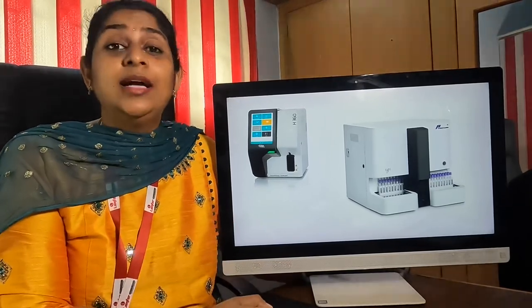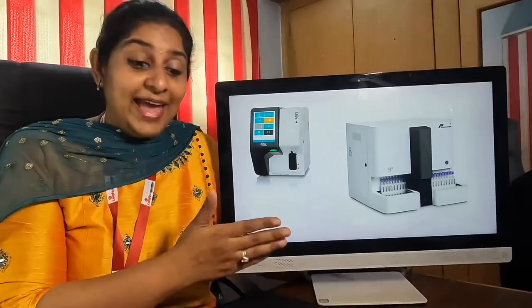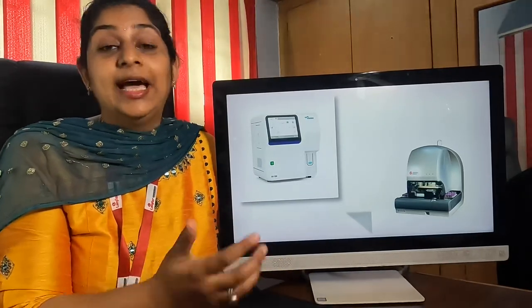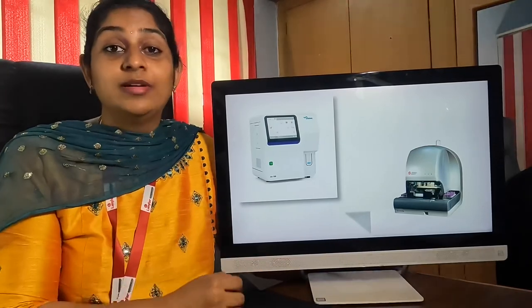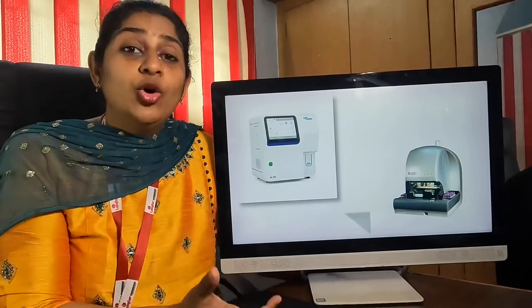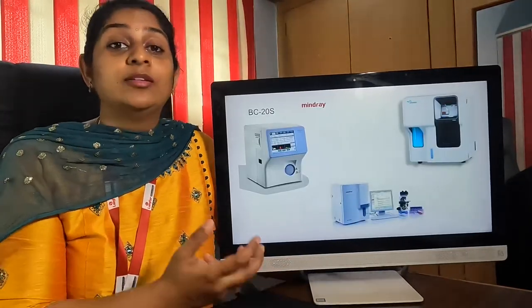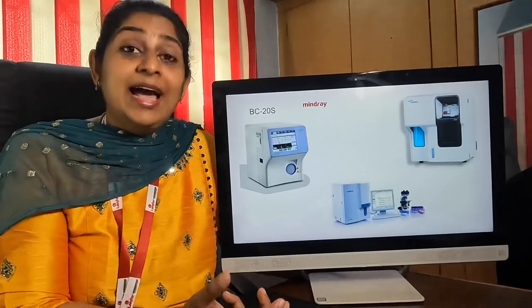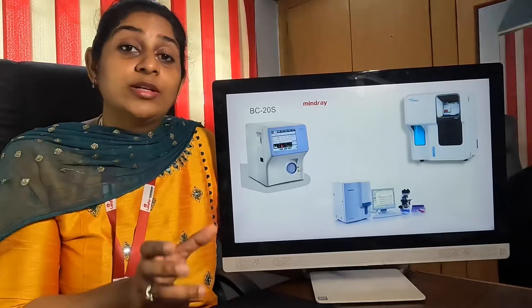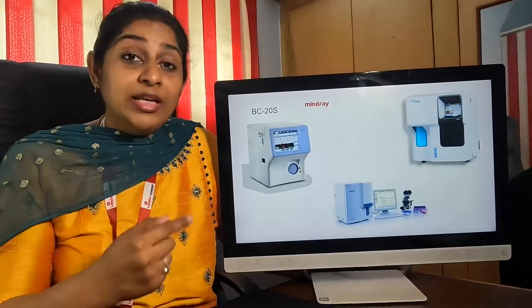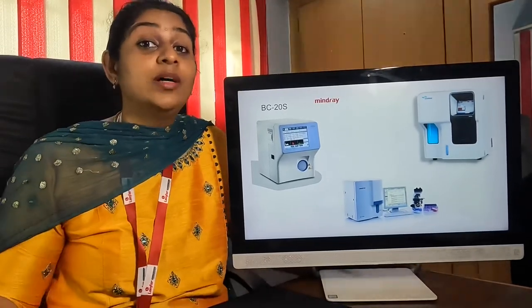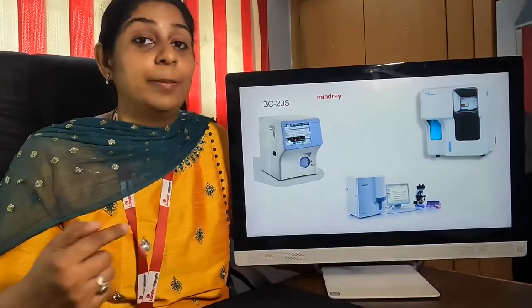The second point is the standby time. Every make of the hematology machine has a different standby time. Some machines have half an hour, some two hours, and some give you around four hours of standby time. The standby time is the time once you have run a sample — it will be on a pause or sleep mode for some time. While restarting, it usually takes the cleaning reagents, thereby increasing the working cost when you run samples after the standby time.